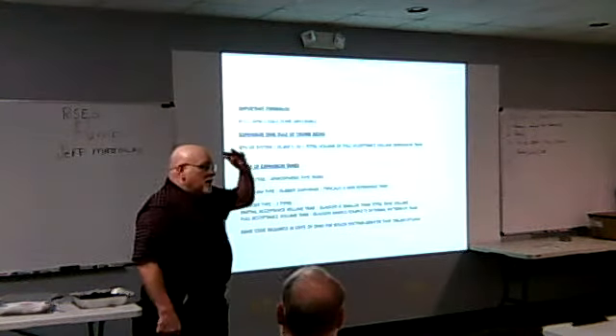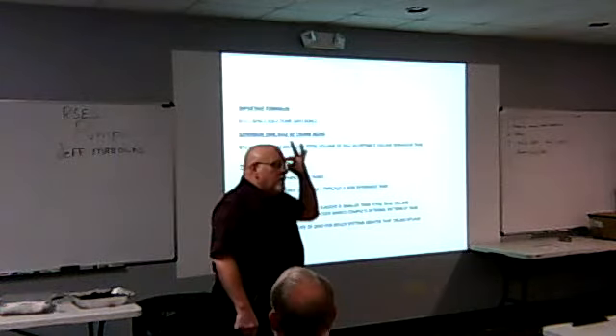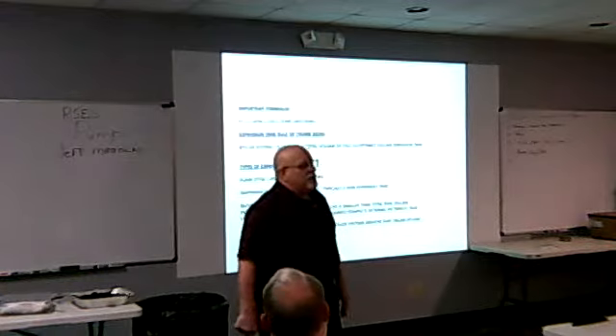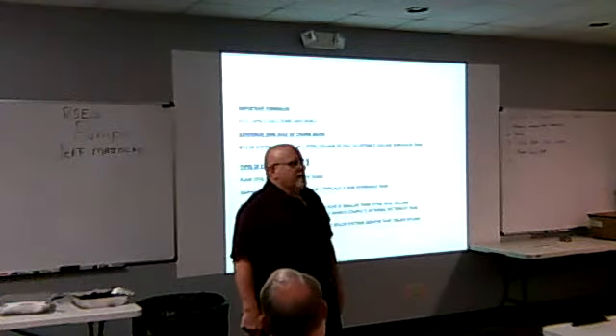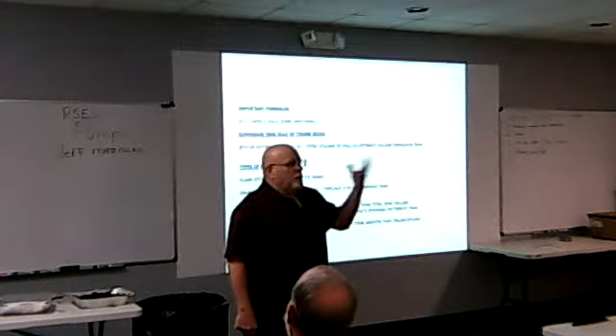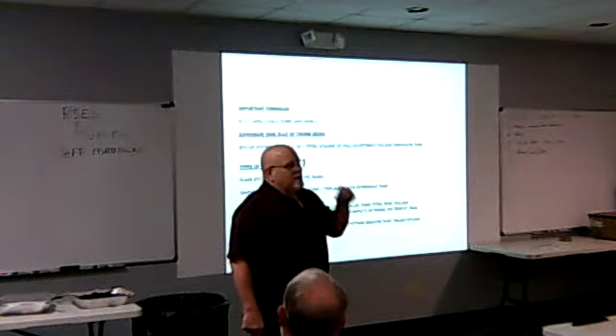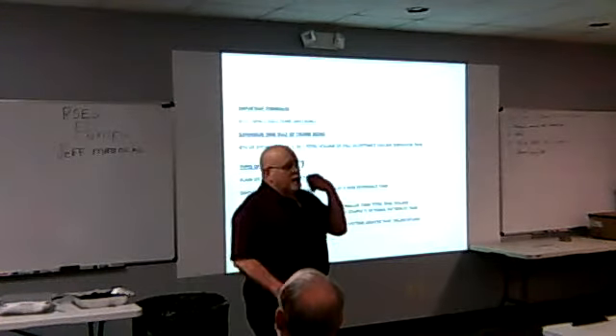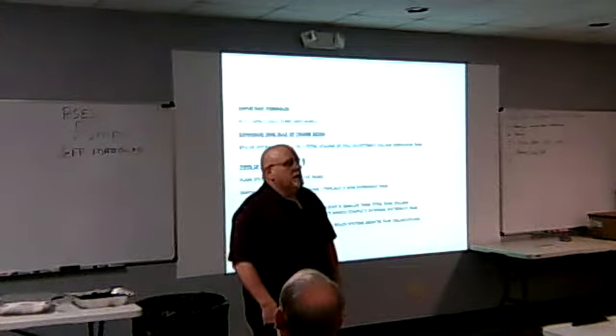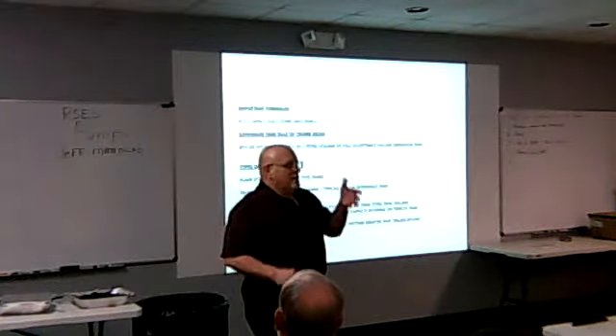With the VFDs, do they have a limit in them to stop them from spinning too fast? No, they're all limited, typically at 60 hertz. When we program our drives, they go 0 to 60, but we'll typically ramp up in 10 seconds, and our minimum speed, whether it's needed or not, goes to 20 or 30 hertz automatic. They just jump right through it. But you can get critical speeds in there and it can really mess with the pump.